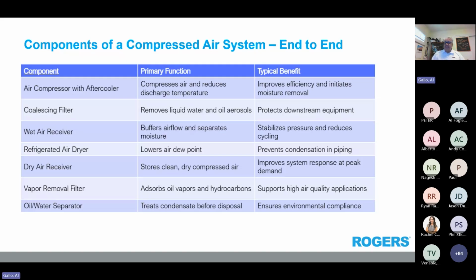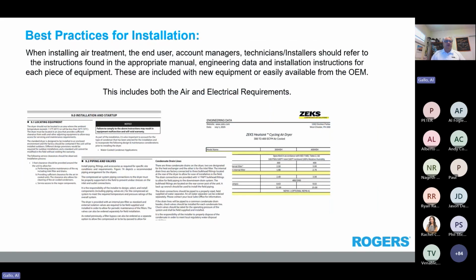So when we go to installation, where's the first place we should look? Pretty much every manual has some section or pages in it talking about how to start, what to do for the installation, how to do the startup, what piping is best application for that thing. And also not just for the air side, but also for the electrical side. What are the electrical requirements? How many BTUs is it going to generate? The dryer, if it's a refrigerated dryer, it's going to generate some heat. If it's a heated desiccant dryer, it's going to generate heat. How many BTUs is it going to generate?